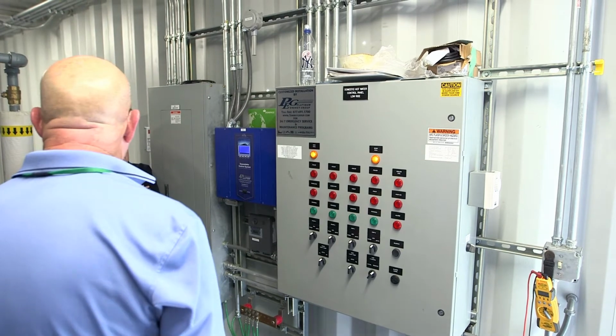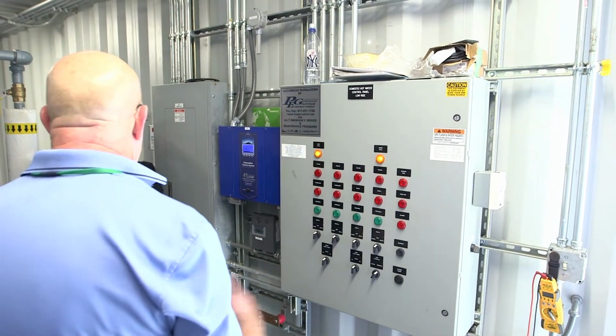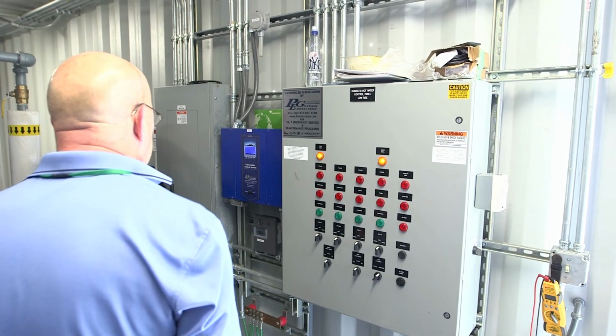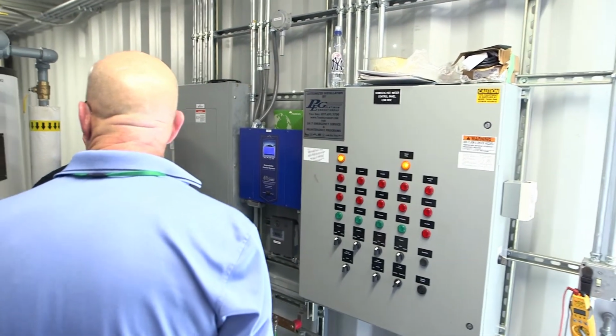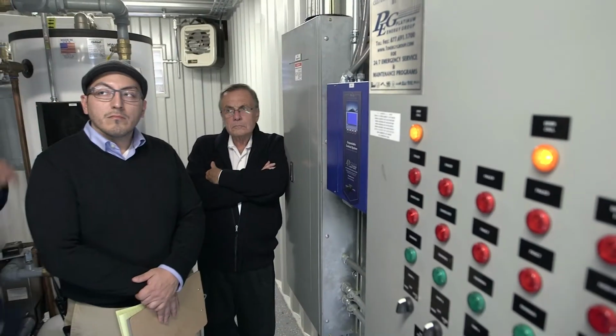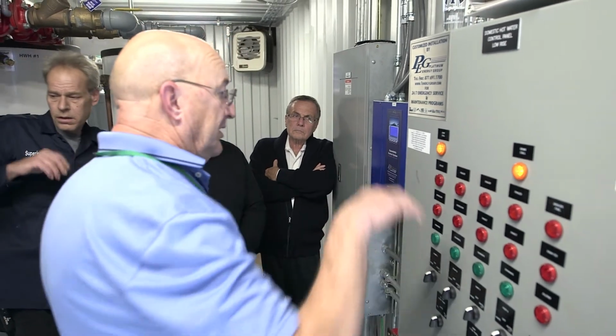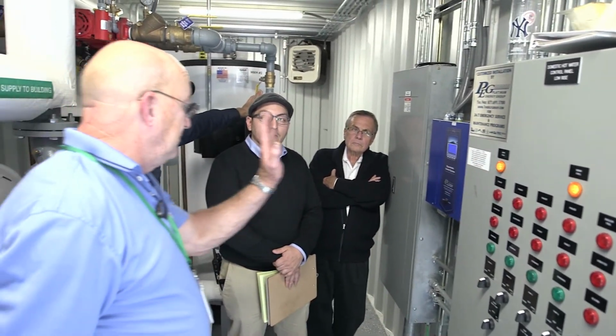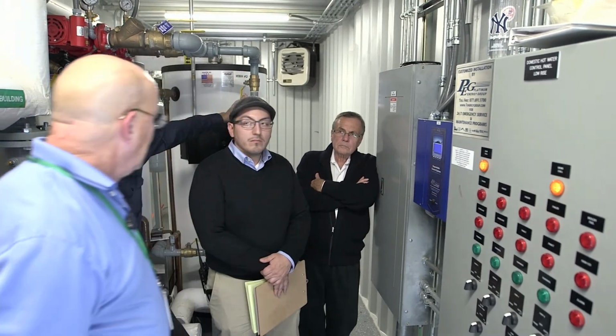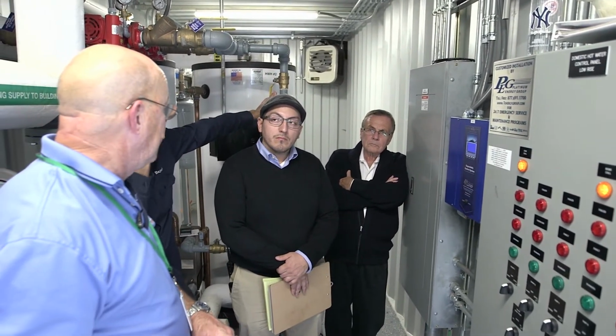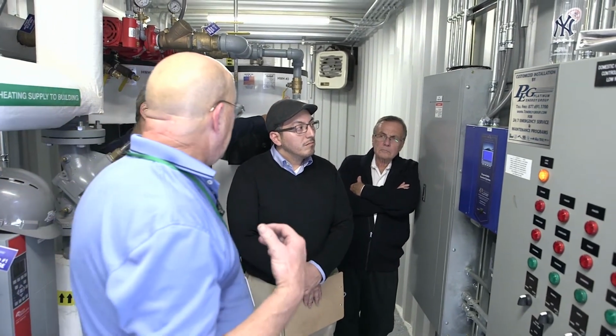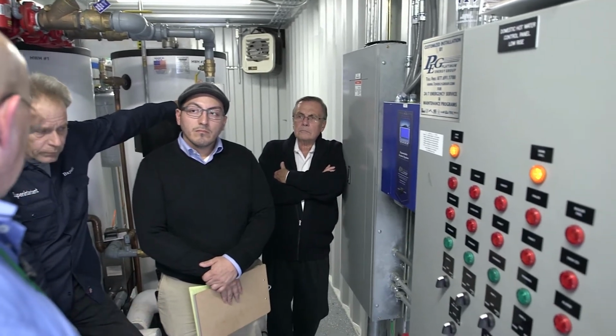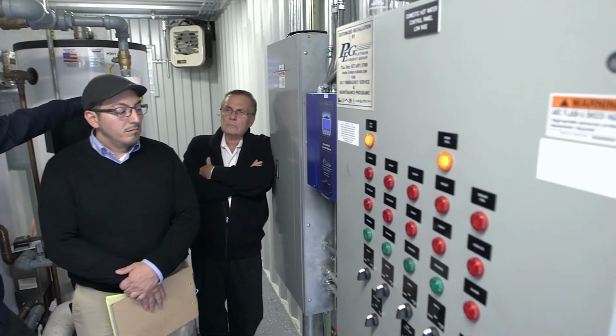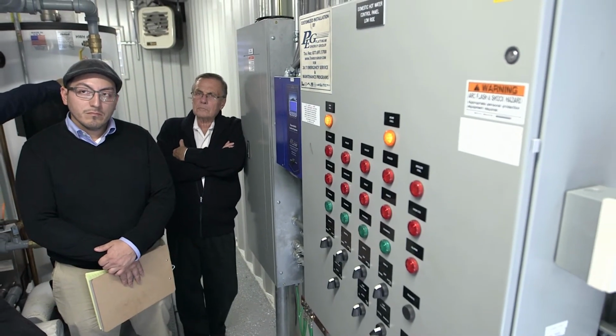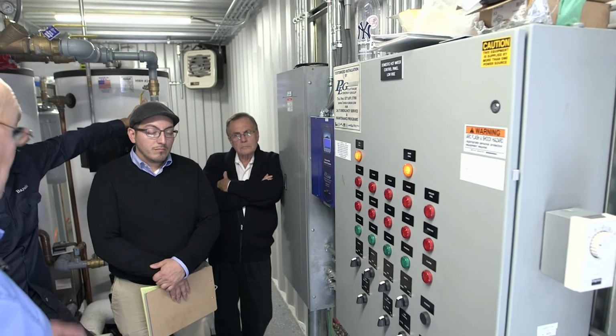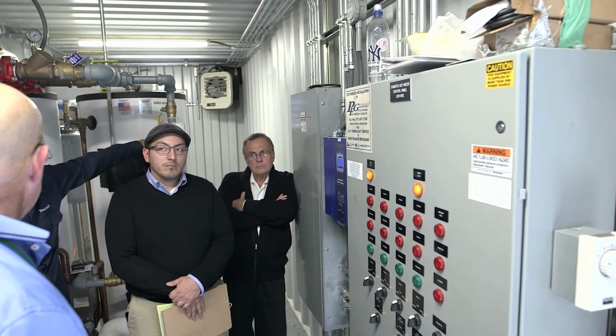It's good for the first year, we're doing everything here. So the best thing you can do is when you have a service call and the service guy is here, watch what he's doing. The only time the boilers will come on if there's no call for heat is if there's domestic hot water. Any call for heat comes through this panel. The panel energizes circulators and the boilers. These boilers will not run at all unless one set of pumps is running. It's a built-in safety that there has to be flow through the boiler for the boiler to run. If there's no flow, the boilers will not run because they'll overheat instantaneously. They heat up that fast.